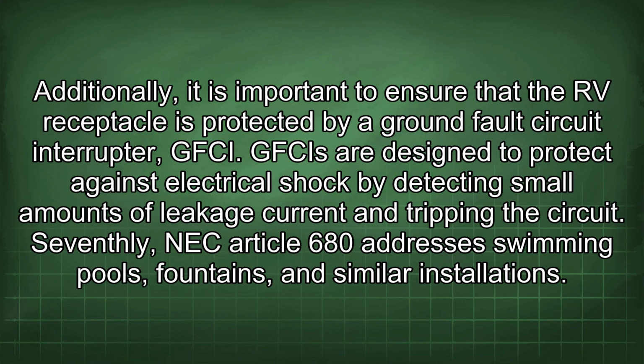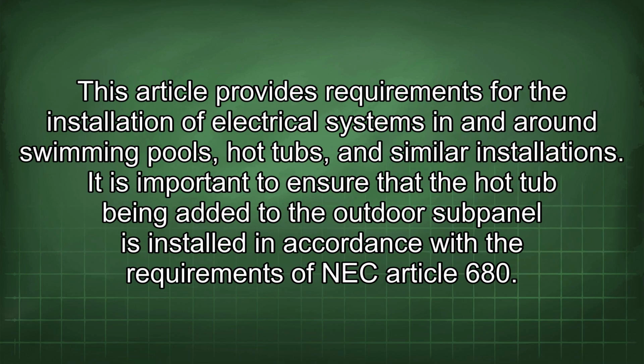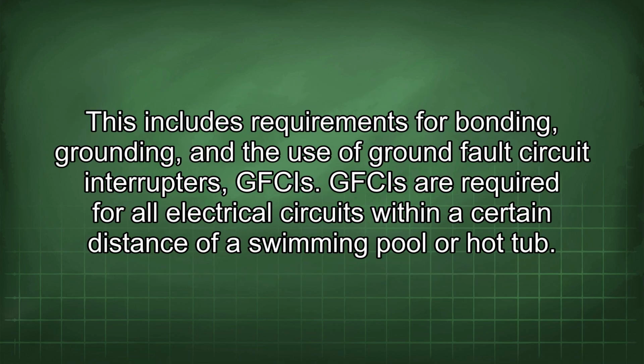Seventhly, NEC Article 680 addresses swimming pools, fountains, and similar installations. This article provides requirements for the installation of electrical systems in and around swimming pools, hot tubs, and similar installations. It is important to ensure that the hot tub being added to the outdoor subpanel is installed in accordance with the requirements of NEC Article 680. This includes requirements for bonding, grounding, and the use of ground fault circuit interrupters, GFCIs.